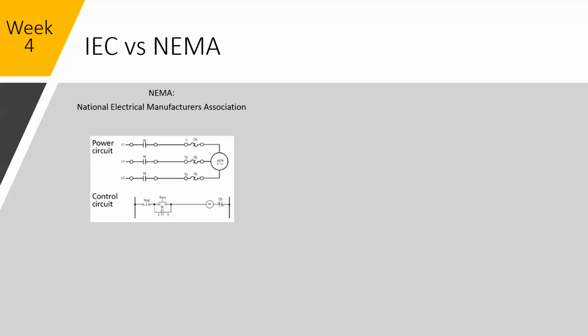Right, IEC versus NEMA. So NEMA stands for National Electrical Manufacturers Association. And NEMA power drawings look something like this. This is a pretty bare bones example of what a motor starter circuit would look like, where you've got your power circuit, line 1, line 2, line 3, a motor starter, T1 and T2 here for your overload relays, T1, T2, T3. This is your motor. And then you've got your control circuit down below: stop button, start, your motor, an overload, normally closed contact of that overload, and then your seal-in circuit.